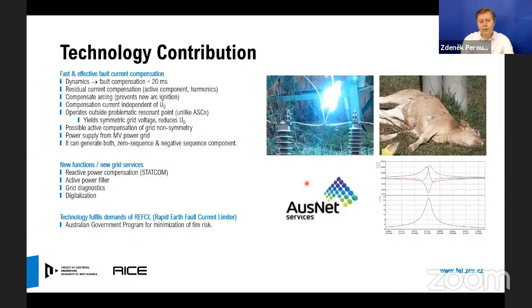We came with new features to the grid, where we are combining the earth fault compensation together with reactive power compensation under no fault operation of the grid. We can secure the active harmonic compensation. We can act like an active power filter. Because we behave like a fully controlled current source installed in the system, we can provide new grid diagnostic features. And we offer for the grid several functions for the digitalization.